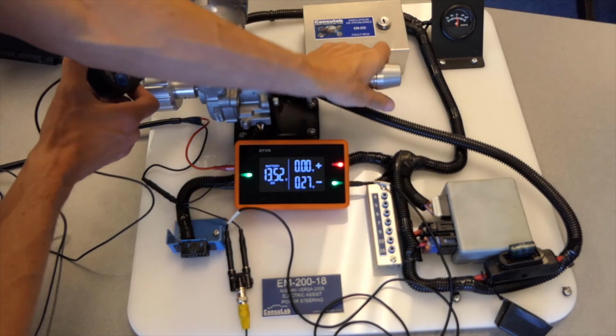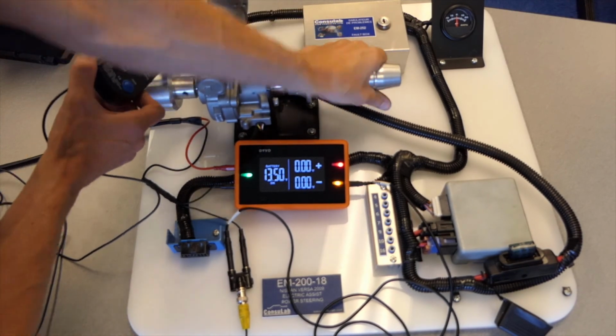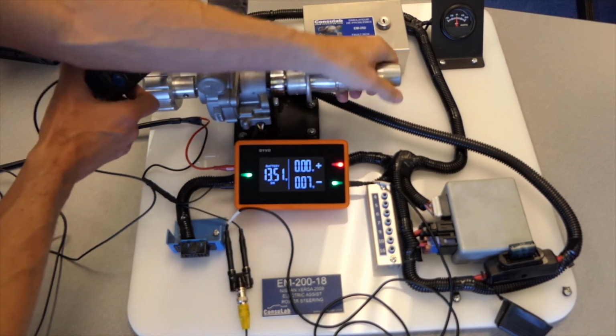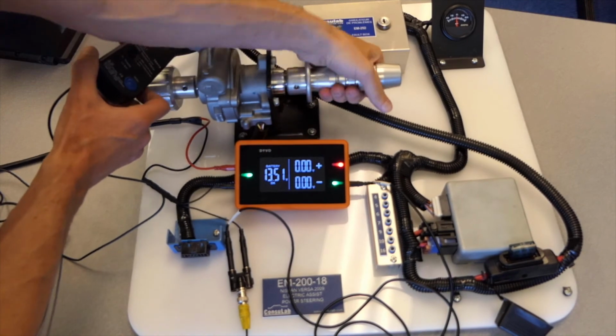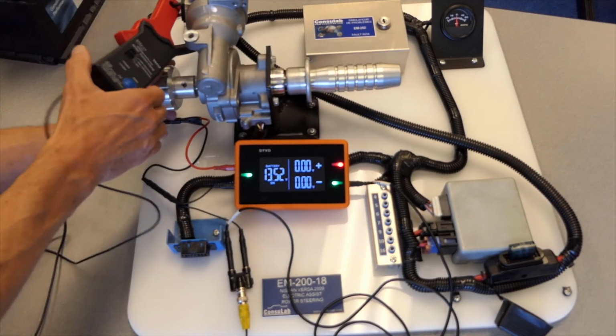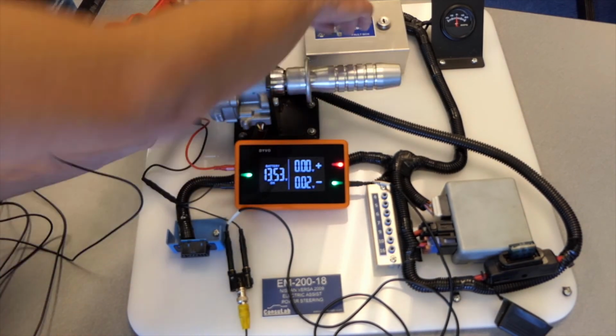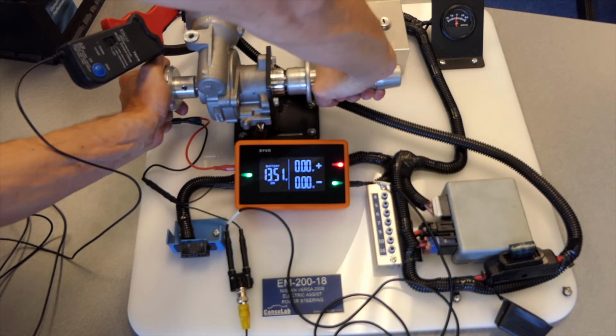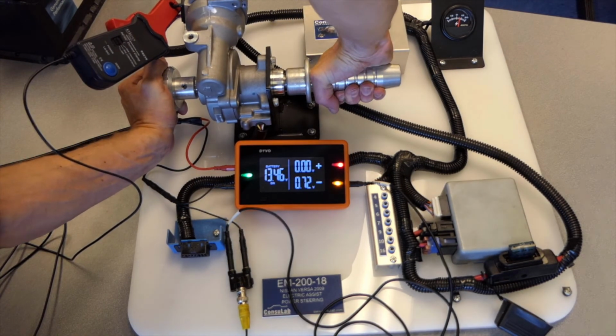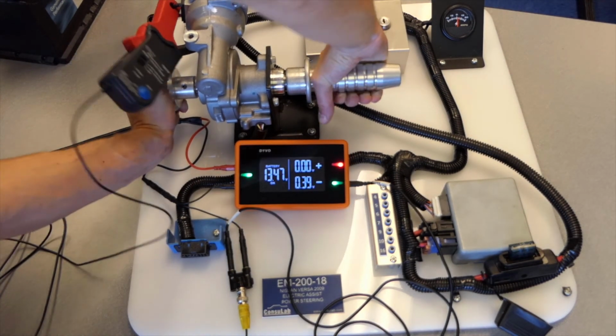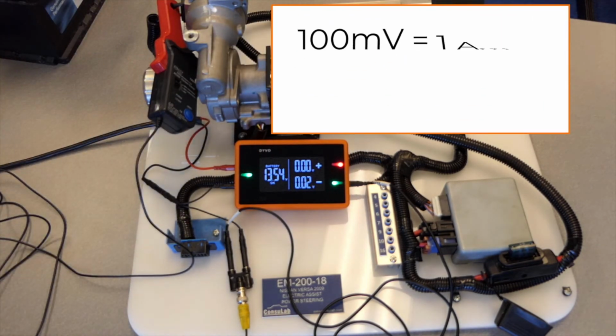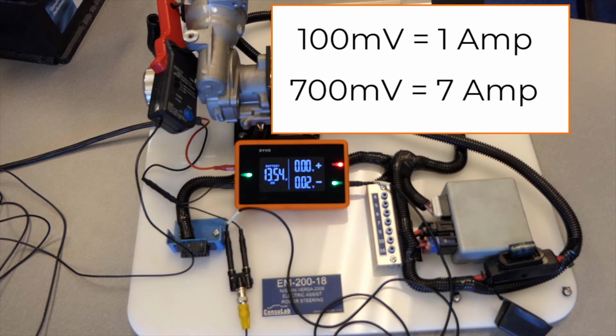Now when I spin this, we can see that voltage jump up, and depending on how much I can really spin this, I saw 0.22, then 0.28. I'm going to try to hold this side here and turn it and see if I can really get it going—there we go, 0.7. So if every 100 millivolts equals an amp, that's 700 millivolts, so roughly 7 amps that this motor is using.